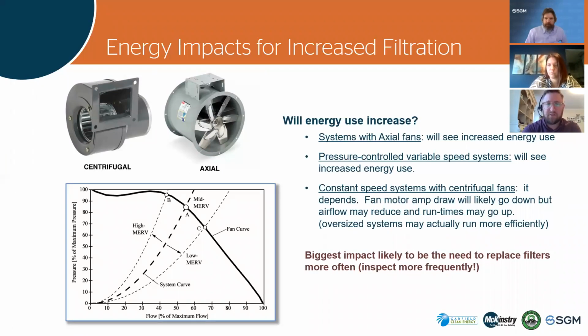And then many systems have constant speed with centrifugal fans. And for these systems, it really depends. What we see here is that the amp draw from the fan motor actually goes down, but run times go up. So you're reducing airflow still, and it may or may not increase your energy use. In the end, the takeaway here, I would say, is your main impact is going to be the first cost of your higher efficiency filters and the fact that you'll need to replace them more often because they'll load more quickly. So we actually recommend you monitor these more frequently after you upgrade them to get a sense for how quickly they're loading, how quickly you'll need to change them out.